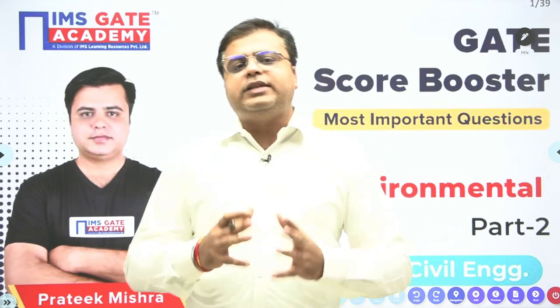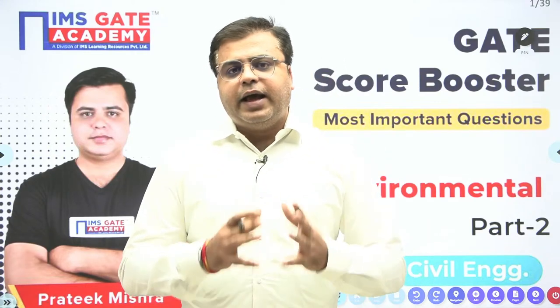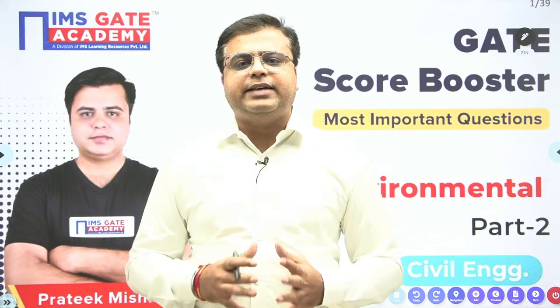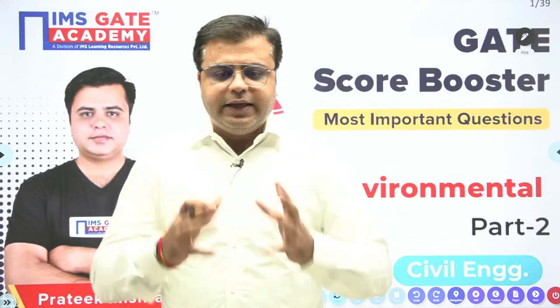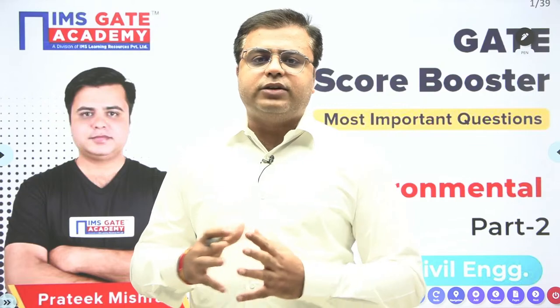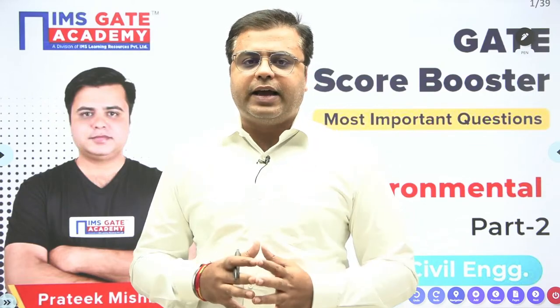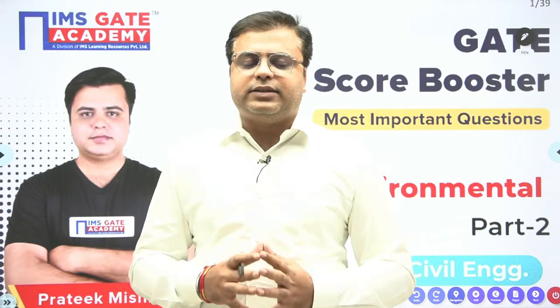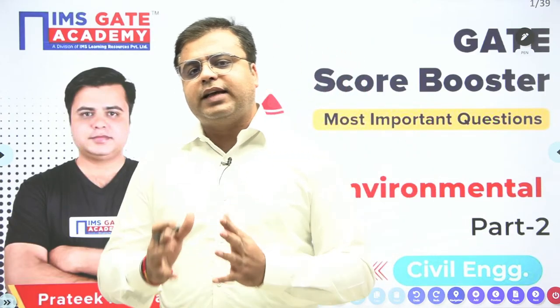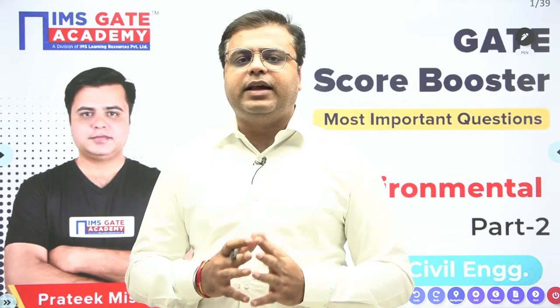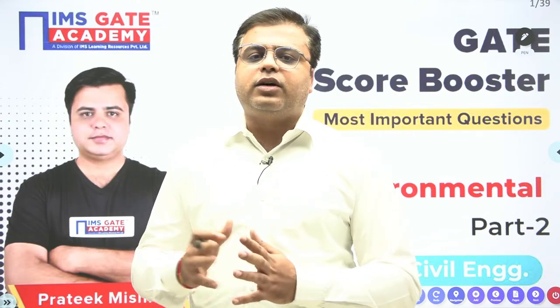In aeration, we bring this water into intimate contact with the air in order to increase the dissolved oxygen concentration. And this dissolved oxygen, being an oxidizing agent, oxidizes the dissolved minerals present, which are color causing minerals also. It oxidizes the organic matter and it removes the dissolved gases as well, right? So this aeration method removes all these three things. First one is dissolved gases. The second one is dissolved organic material. And third one is color causing compounds.